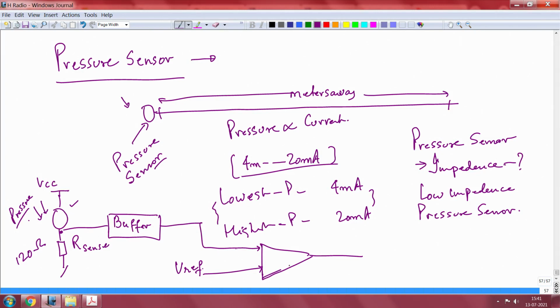Now again you are battled with the same question: what should be the Vref? That is not very difficult if you know the range of pressures you are likely to measure, the minimum and maximum pressure you are likely to read. That will give you some analog output. You know that full scale is the maximum output voltage you will get, and min and max will be known from there.